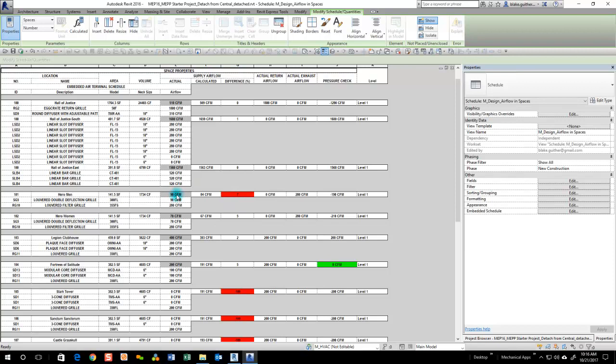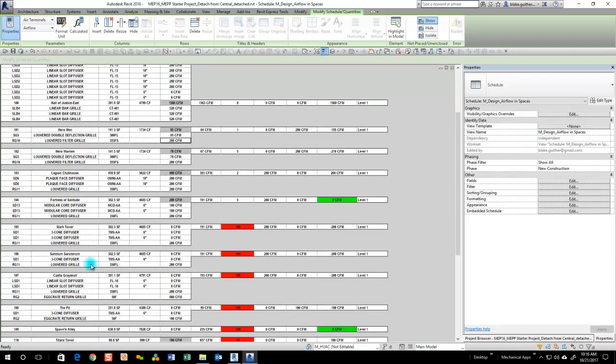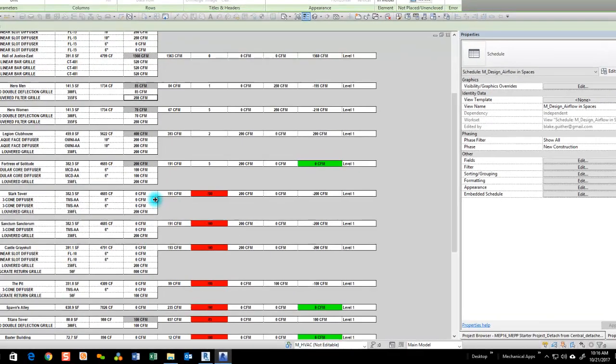But this room here, okay, sure. Let's change this to 85 CFM. That was in the men's restroom, actually where the heroes go to the restroom. That looks good. So now we're not so concerned with plans or where a diffuser is exactly located. We have all the spaces in a model, and you could balance a building very fast. Now we've got two 3-cone diffusers here.